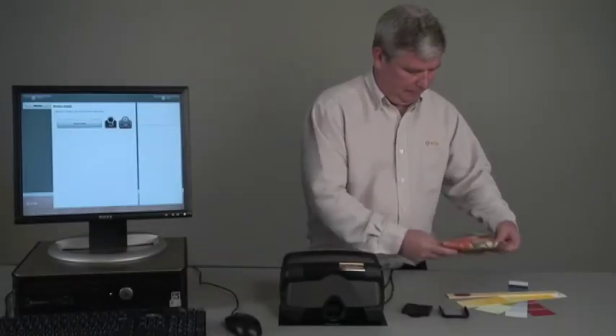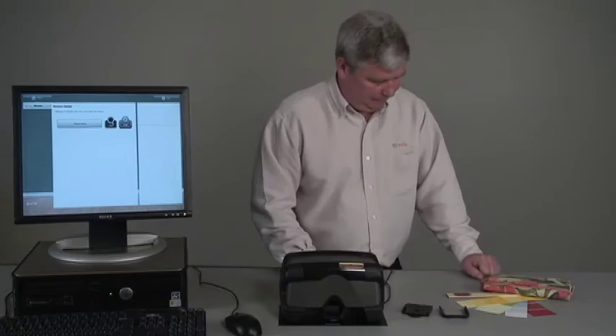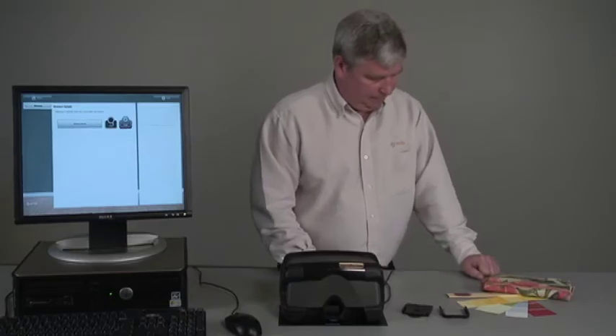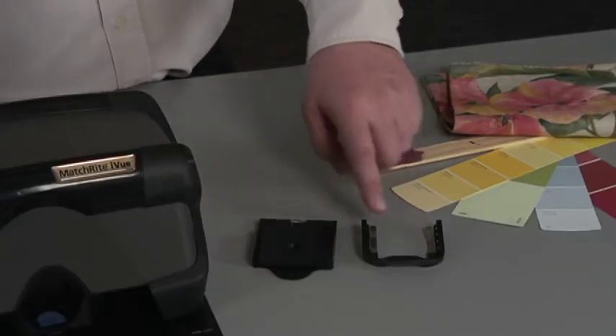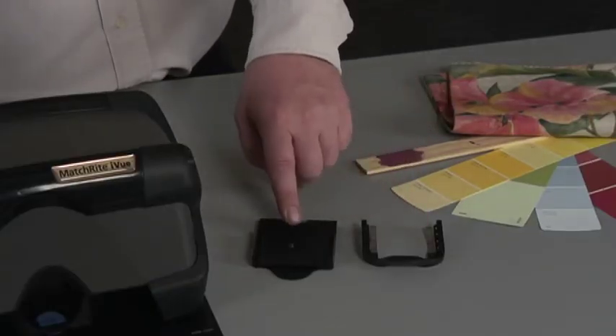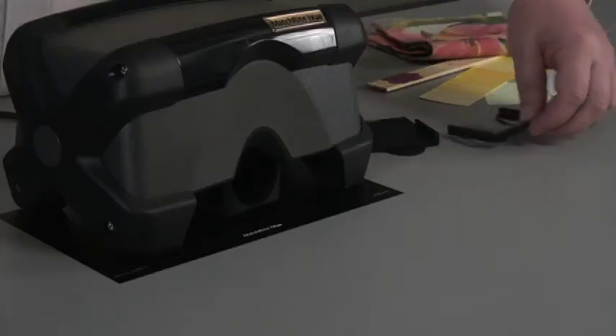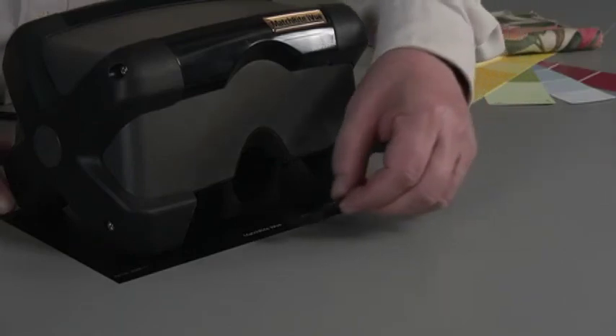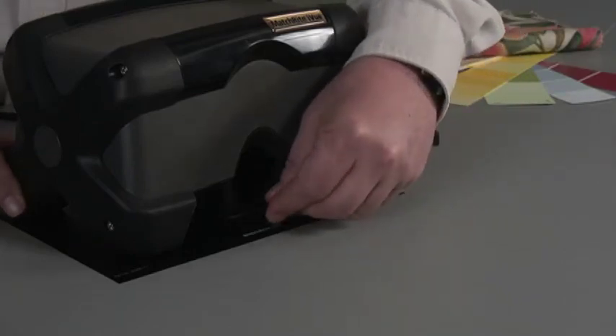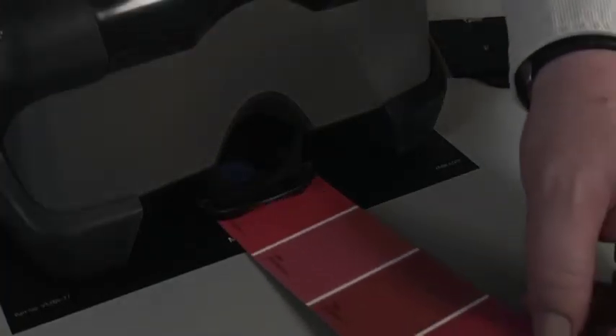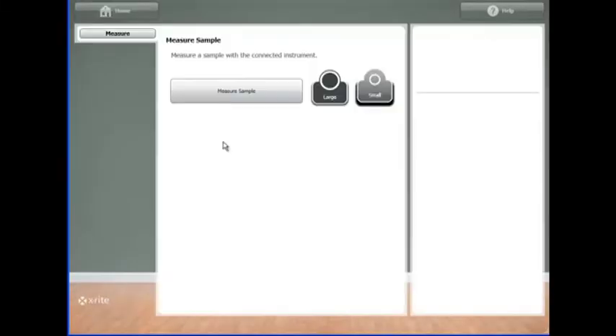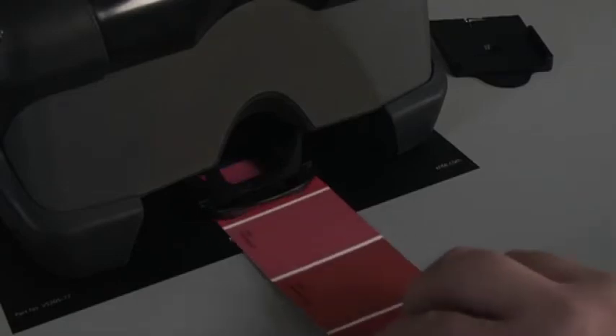The iVue has many features and functions that will help us get the best color match possible. To do this, we'll use our sample holder and chip clip. The instrument has the capability of measuring a 12 millimeter or 6 millimeter sample. We simply slide the sample holder on the bottom rail of the instrument. This ensures that a color card sample is flat, with no curved edges. For example, click on the color match in Color Designer Plus. Place sample underneath the sample holder, which now gives us active visual targeting for precise color measurement.